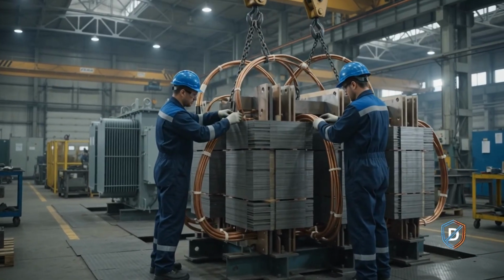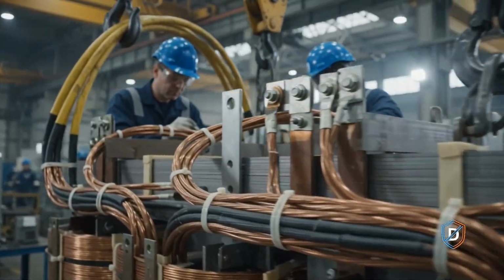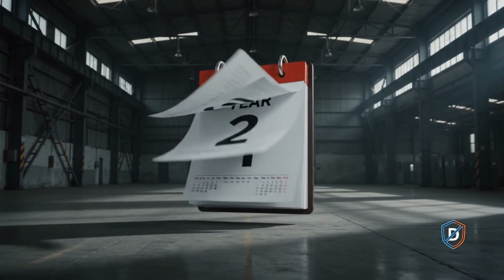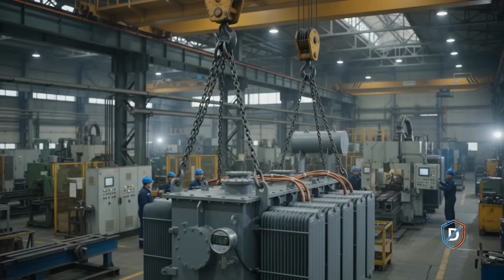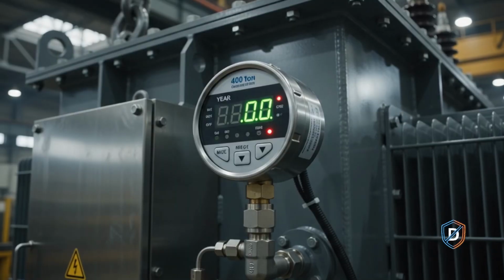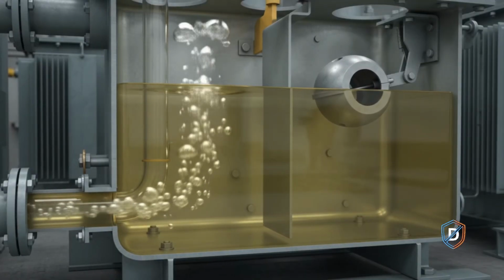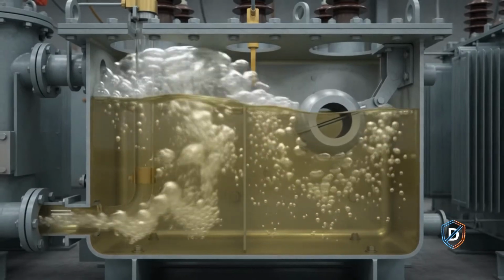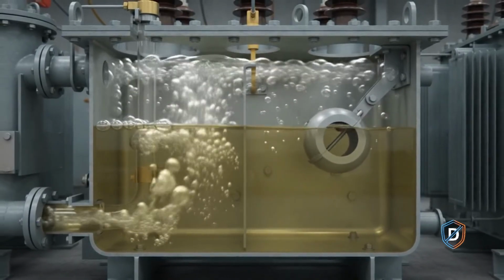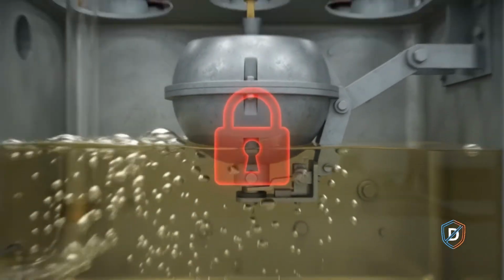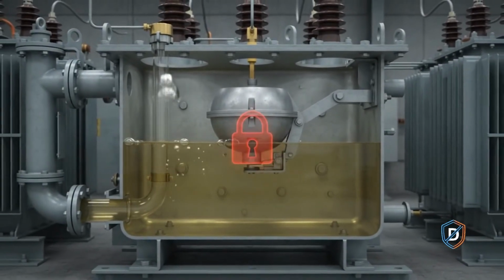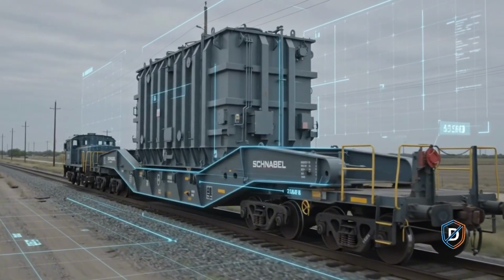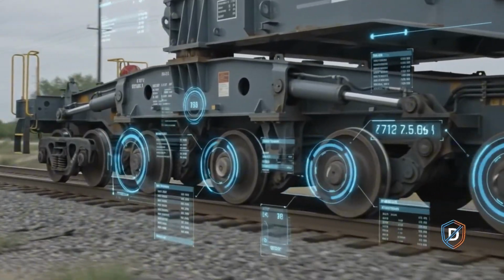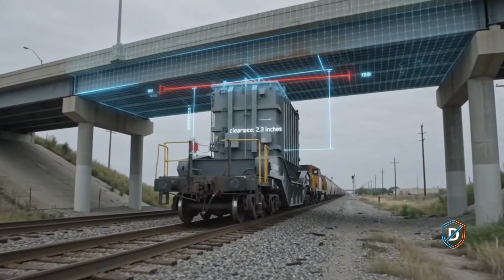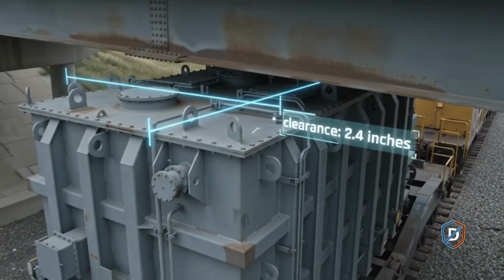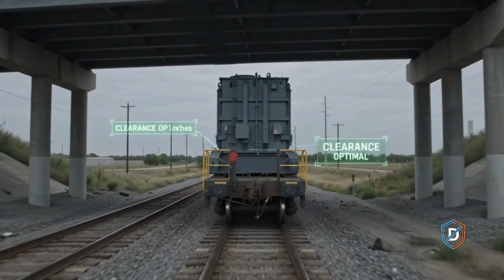You can't just replace a 400-ton transformer. Manufacturing takes up to 3 years, with zero spare inventory. Inside the transformer, gas accumulation triggers the mechanical Buchholz relay, locking the unit down completely. Moving a replacement requires specialized Schnabel railcars, custom route permits, and cleared bridge clearances.